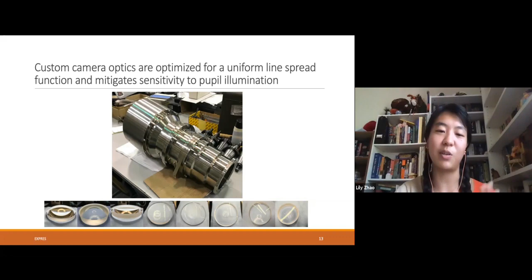Zemax to see how light will go through the instrument. And there's a checkbox you can check to maintain a uniform line spread function, or mitigate sensitivity to pupil illumination, and also one for minimize the number of optical elements, and he just left that one unchecked. So this was his pride and joy, and these 8 lenses make sure that the way that the light spreads out across the detector is very uniform, and if it does change, it changes smoothly, which is very important for lines looking similar no matter where they appear on the detector.